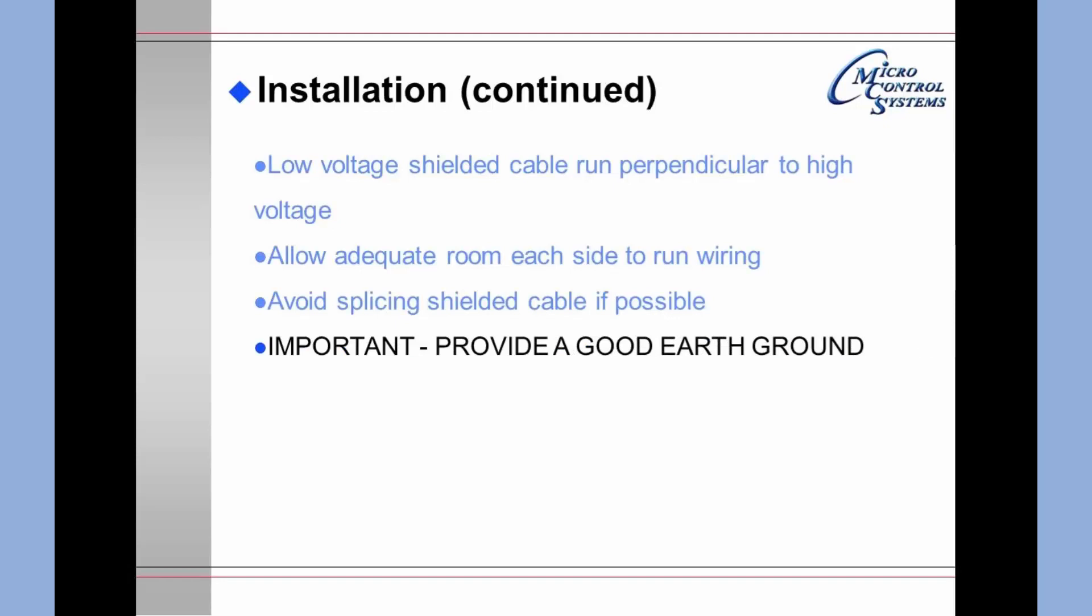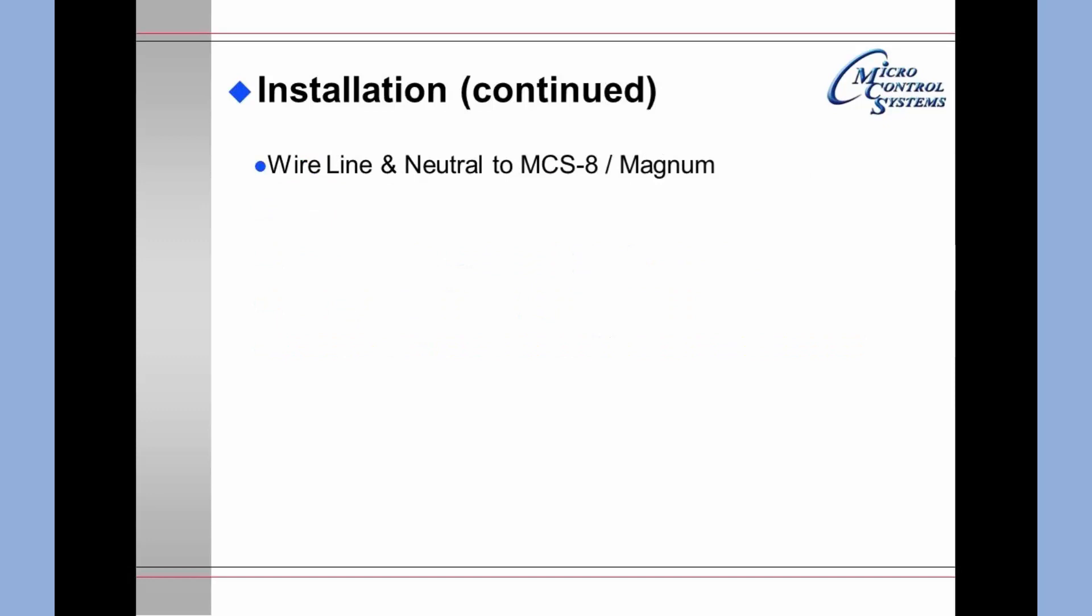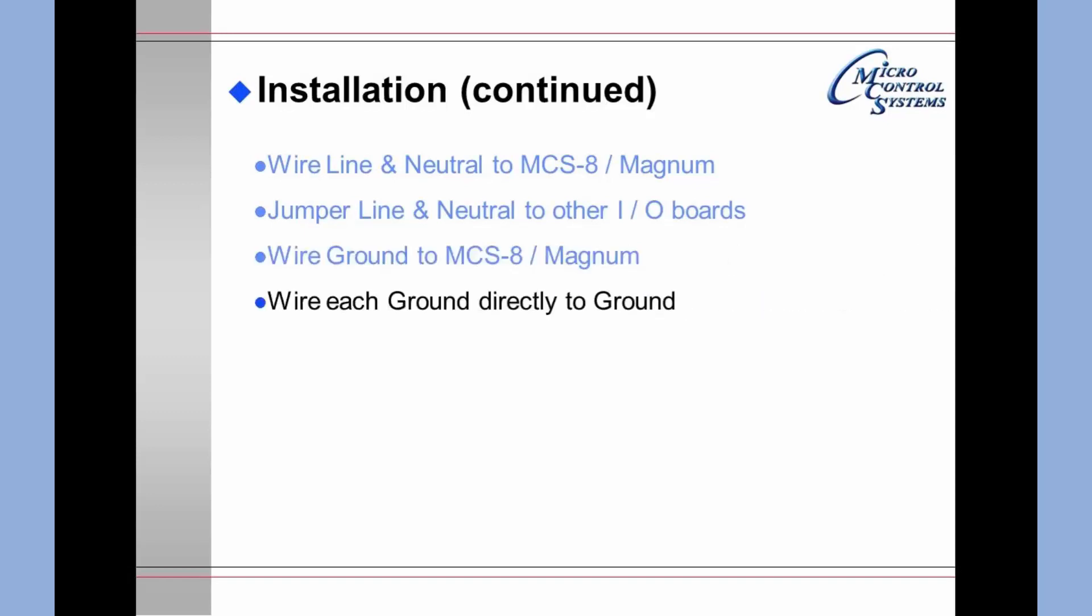Important: provide a good earth ground. When doing the wiring, you may wire the line and the neutral to the MCS-8 or the Magnum, and then you may jumper the line and neutral to all of the other input output boards. You will wire the ground to the MCS-8 or the Magnum, and then you will wire each switch ground directly to ground. Important: do not jumper the grounds. A ground wire should be connected to each board and then directly to ground.